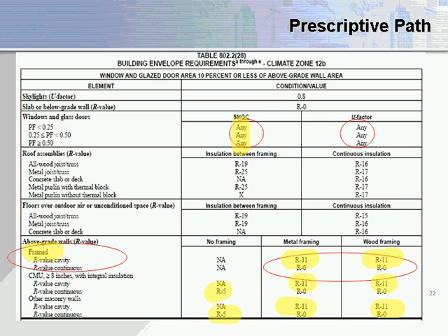We can essentially put in any window we want to between those two assemblies from an IECC standpoint. Now, there might be other IBC requirements on what that glass must be made of and things like that, but from an energy code standpoint, under Climate Zone 12B, essentially we can put in any U factor or SHGC glass door, opaque door, or window between those spaces.